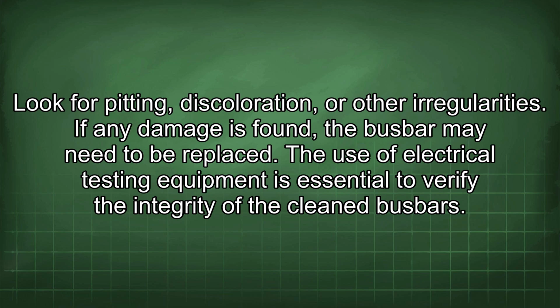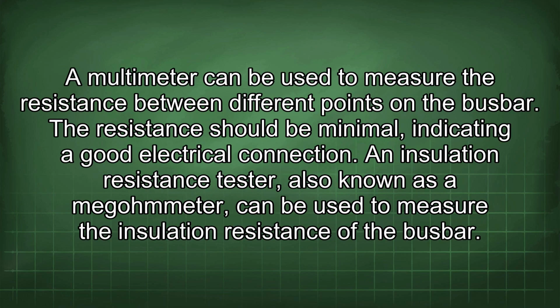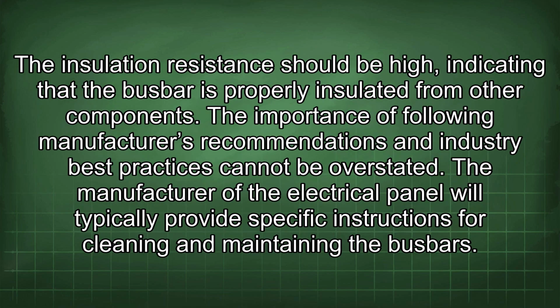The use of electrical testing equipment is essential to verify the integrity of the cleaned busbars. A multimeter can be used to measure the resistance between different points on the busbar. The resistance should be minimal, indicating a good electrical connection. An insulation resistance tester, also known as a megohmmeter, can be used to measure the insulation resistance of the busbar. The insulation resistance should be high, indicating that the busbar is properly insulated from other components.